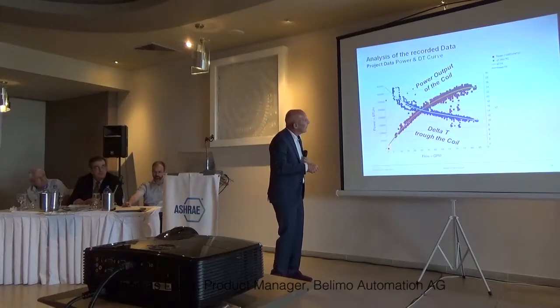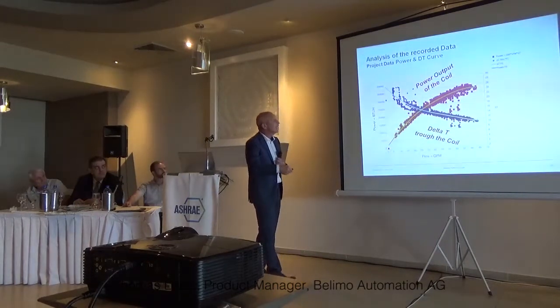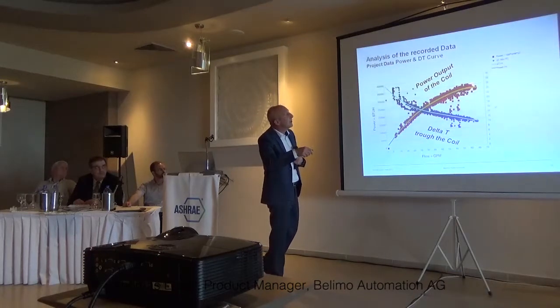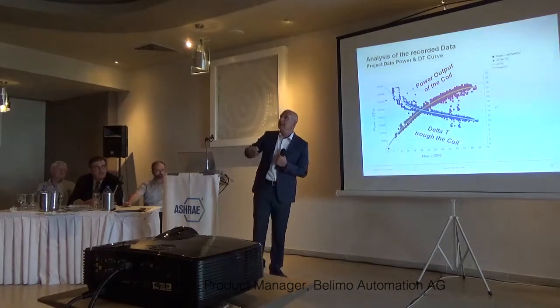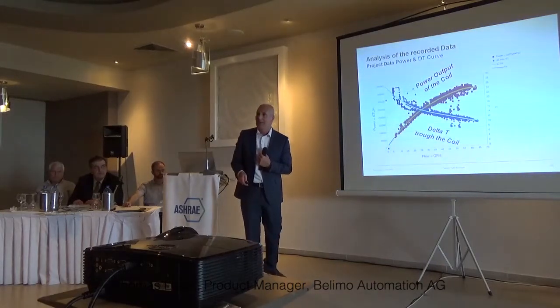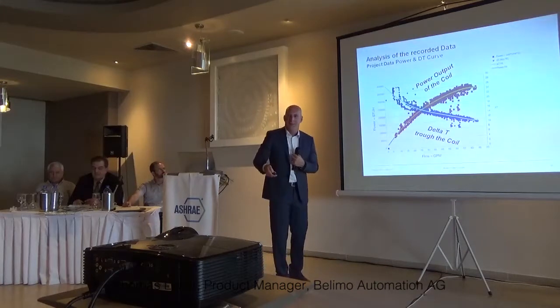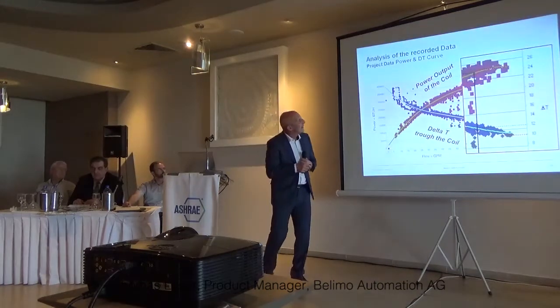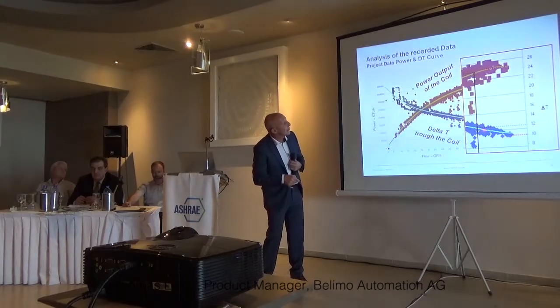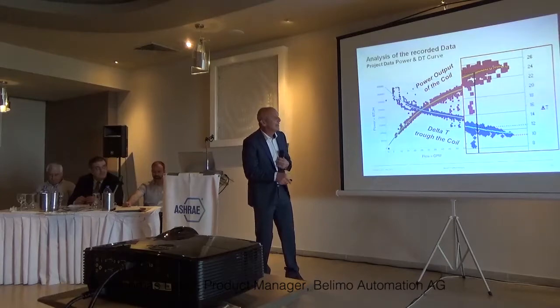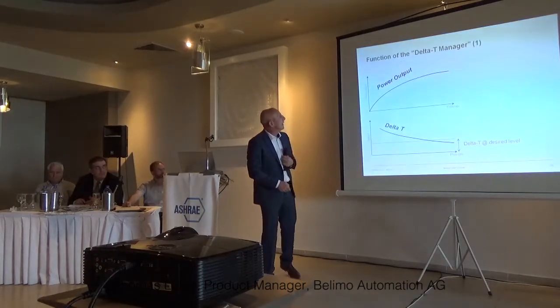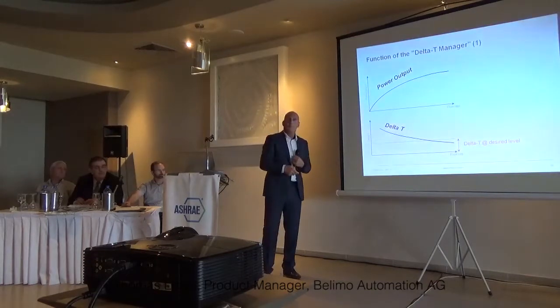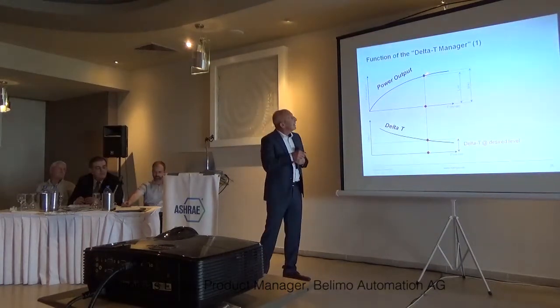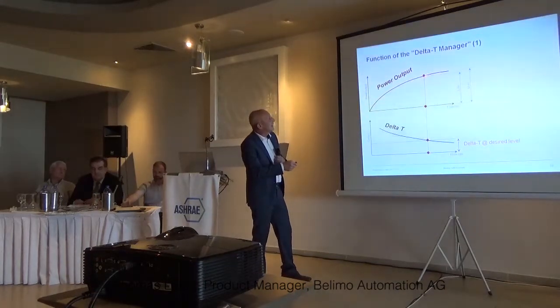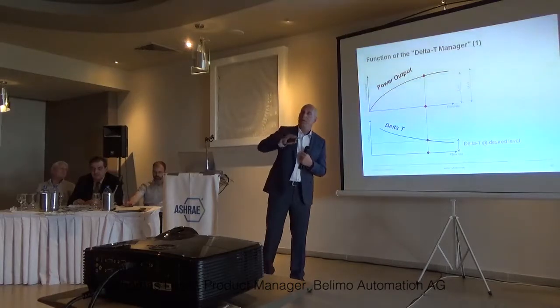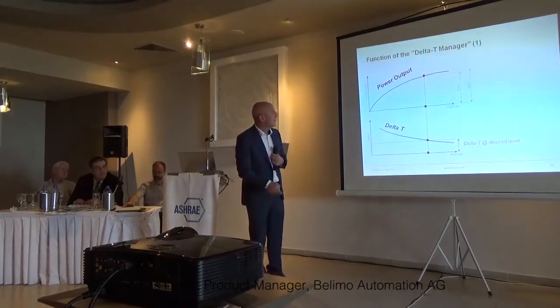But what you can see here as well is that the performance curve of my air handler is not linear. It's convex, and there is a point where it makes no sense to put more water in. There is no more output. The curve will not grow. The only thing that will even decline is my delta T. The same curve, just put into two. This is the convex part. This is more or less the flat part where I don't have any increase in power.